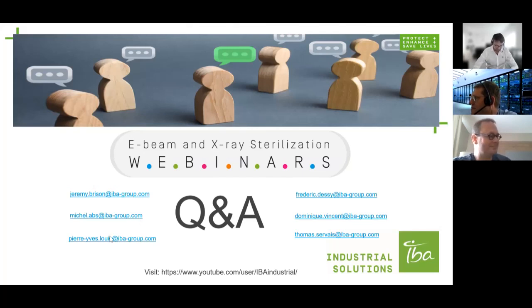A lot of very good questions today. The pulsing mode was the biggest innovation of IBA for the accelerators. It was another great idea from Michel, which allows energy savings, making more compact accelerators, making the high energy that I talked about. But for X-ray, it doesn't really impact the process. The reason is that the beam power is so high compared to the cavity power that you cannot save any more energy. So the electrical efficiency of a TT1000 is above 50%, and pulsing would not help to further increase that.